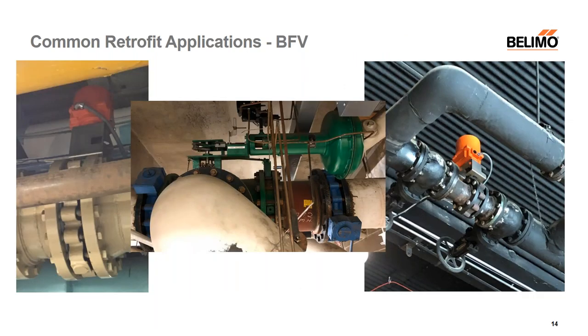Another butterfly valve application would be in a bypass situation — where a butterfly valve controls the flow of water and you want it to bypass either a piece of equipment or from one room to the next. Butterfly valves are very commonly used for these, both in two-way and three-way configurations. In the center of the screen you can see a common-looking three-way butterfly valve with a very large pneumatic actuator installed on top. We can simply replace that with one of our retrofit kits, simplifying things, giving you better control, and eliminating all that maintenance required for pneumatic actuators.